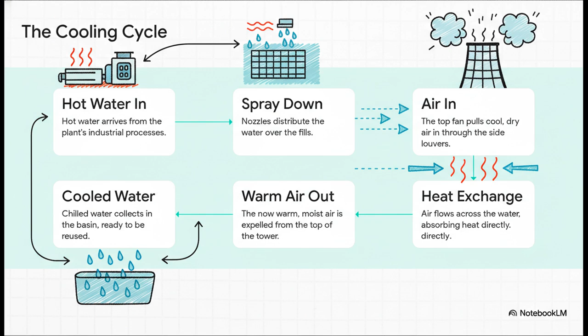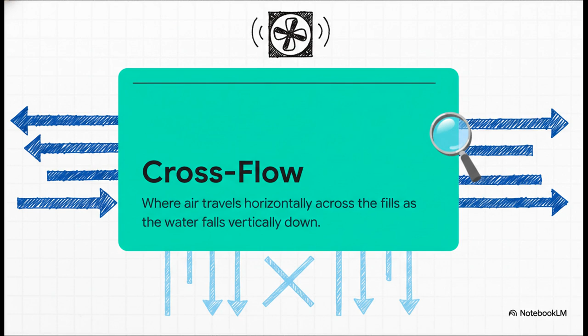This diagram shows us something really important about the design. It's called cross-flow. See what's happening? The water is falling straight down, vertically, but the air is being pulled horizontally, across it. Their paths literally cross each other, and that's why these are often called cross-flow cooling towers.